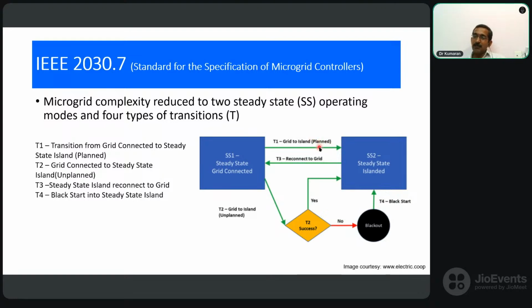This is what we refer to as planned transition. So we know the time at which this transition is going to be needed, and we keep some of those DERs warmed up. We don't go for a cold start. When the time of that planned outage comes, we smoothly transit from the steady state grid connected state to islanded mode. It is going to be smooth.